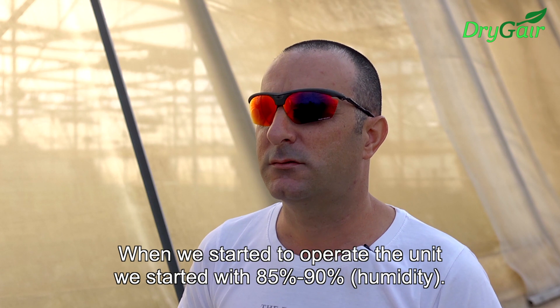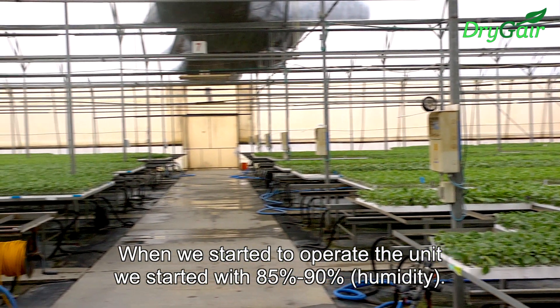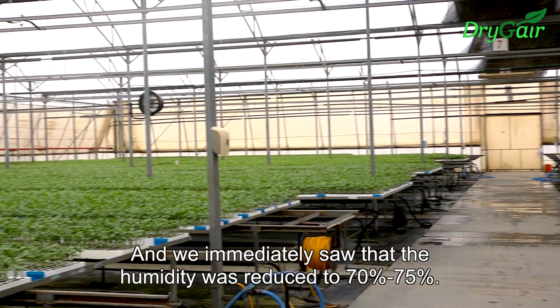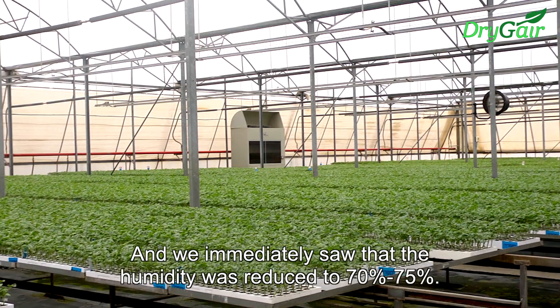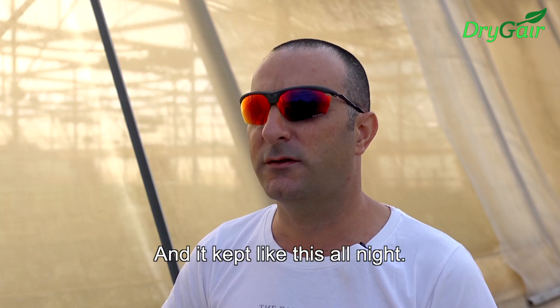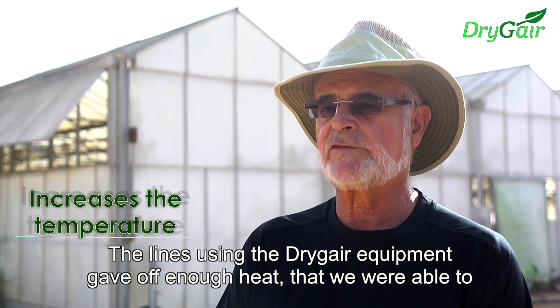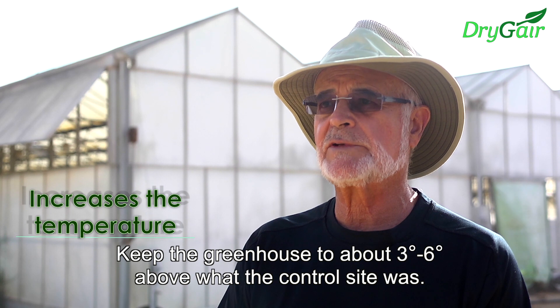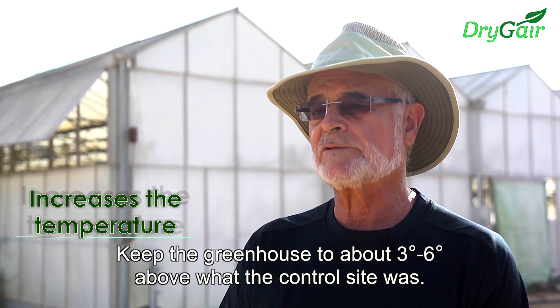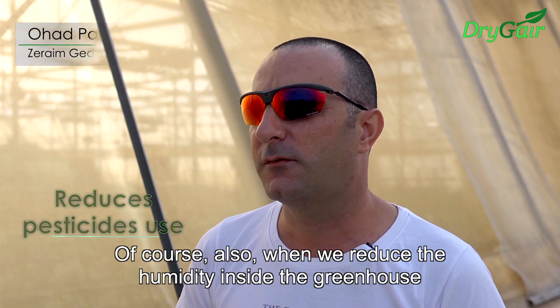When we started to operate the unit, we started from 85-90% humidity and we immediately saw that it reduced to 70-75%, and it kept like this all over the night. The lines using the DryGair equipment gave off enough heat that we were able to keep the greenhouse about three to six degrees above what the control side was.